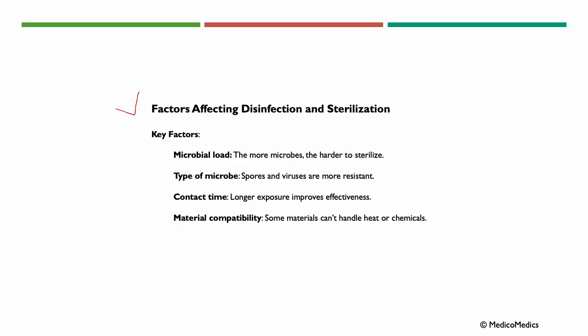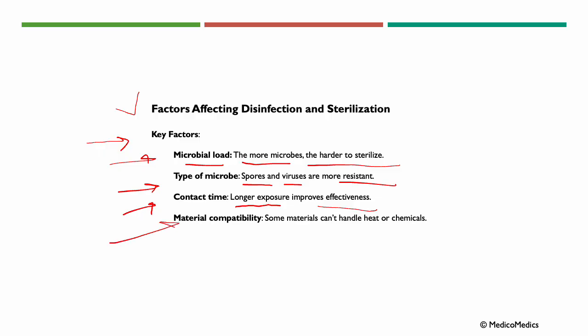Factors affecting disinfection and sterilization include microbial load — the more microbes, the harder to sterilize. The type of microbes matters, as spores and viruses are more resistant. Contact time is also key, as longer exposure improves effectiveness. Material compatibility is another factor, since some materials cannot handle heat or chemicals and need special care to avoid damage.